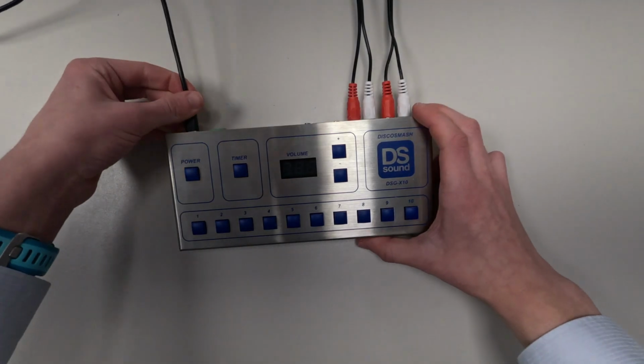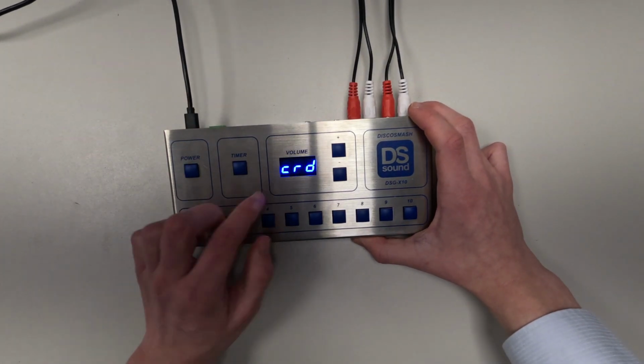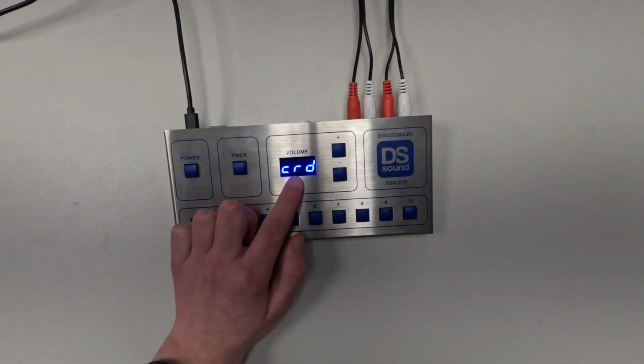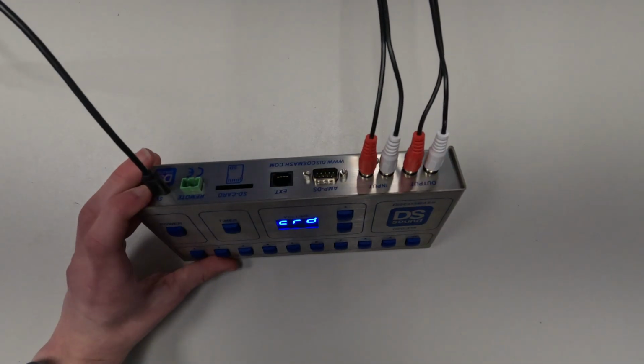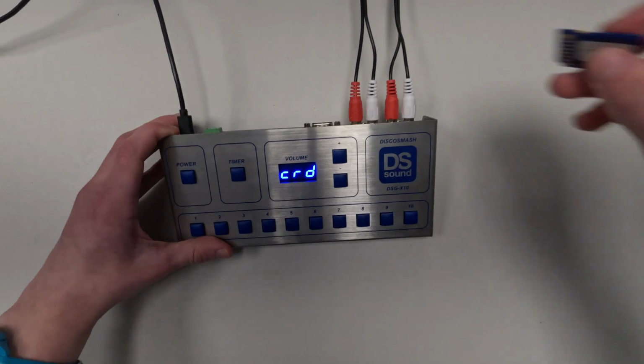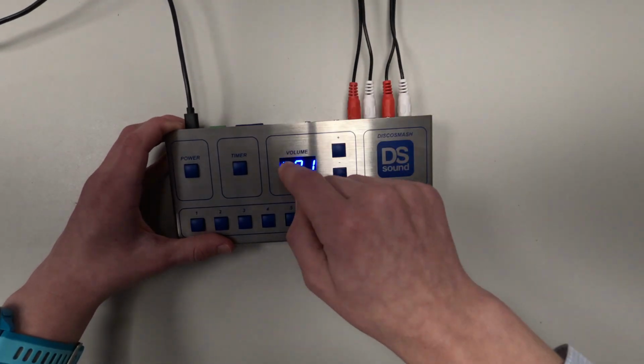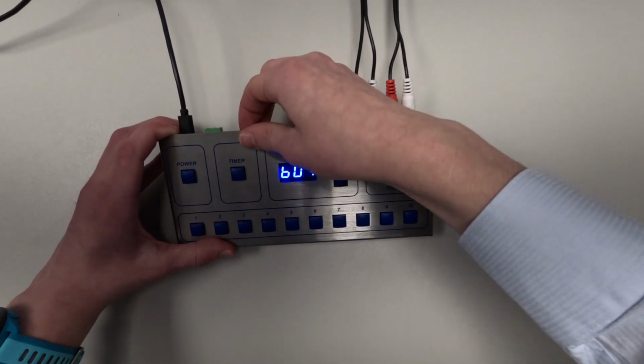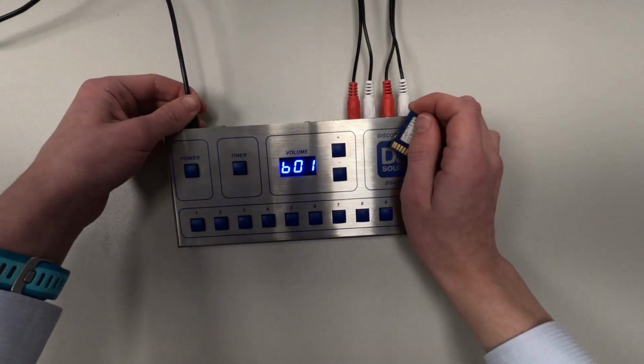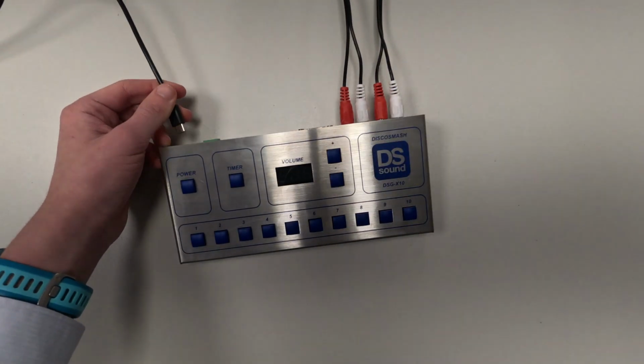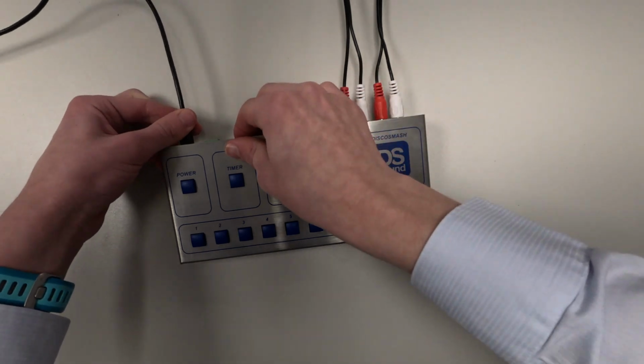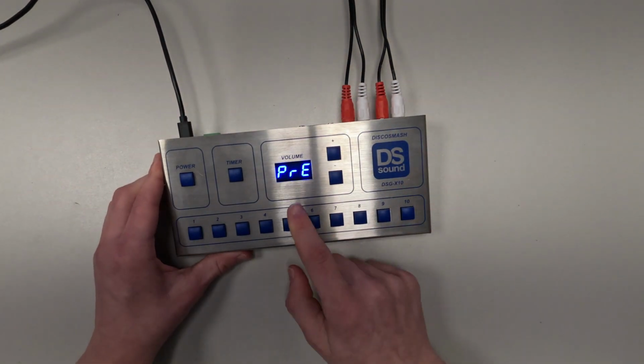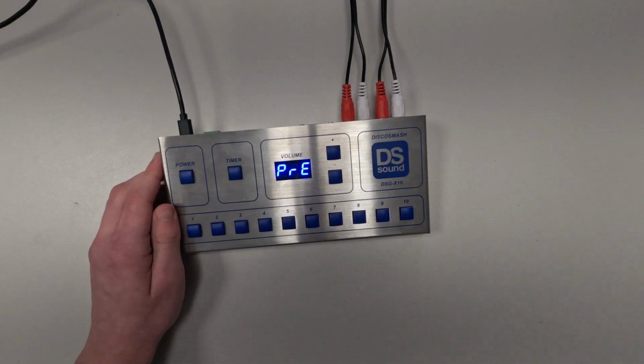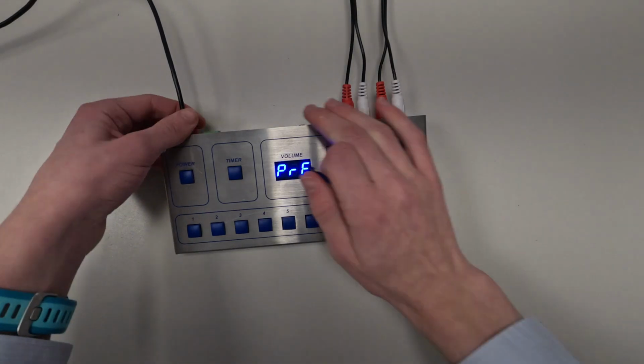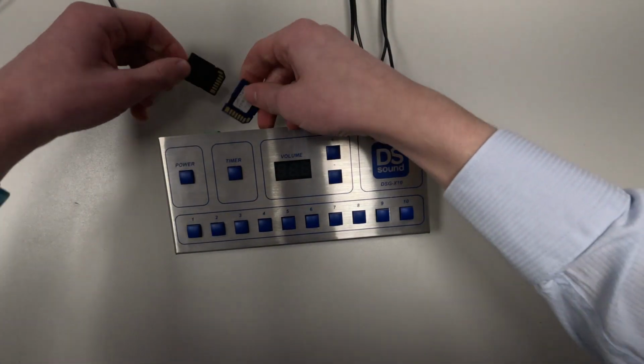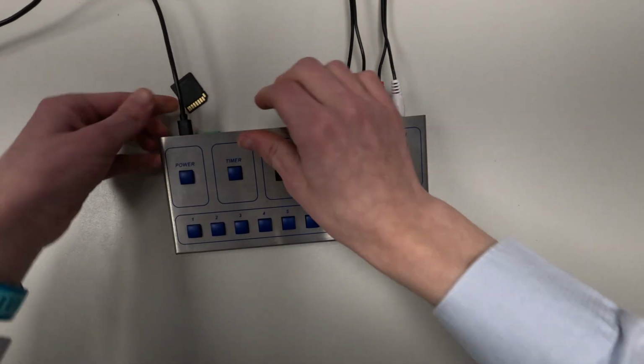Finally, the errors. There are 3 error codes. We'll start with CRD. This error code indicates that no SD card is found. First, check if an SD card is inserted in the device. If there is an SD card, try inserting and removing it several times. The second error code is PRE. This error code indicates that an SD card is found, but that it doesn't contain the correct files or even none at all. Use dsconfig to reformat the SD card.